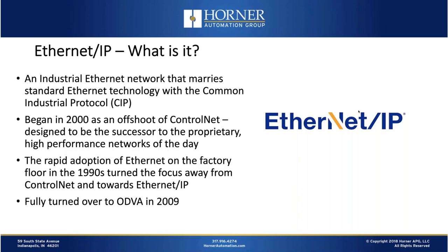So what is Ethernet IP? In a good definition, it's an industrial Ethernet network that marries standard Ethernet technology with what's called the Common Industrial Protocol, or CIP. When I say standard Ethernet technology, I mean there's really nothing special hardware-wise that you have to purchase to implement Ethernet IP — industrially hardened in many cases, yes, but standard hardware. It has its origins in something called ControlNet.